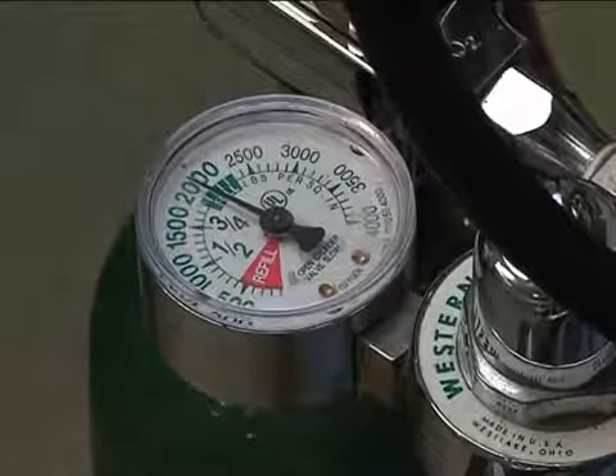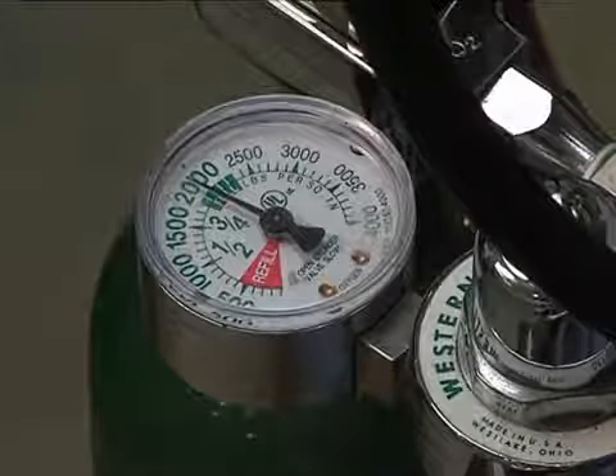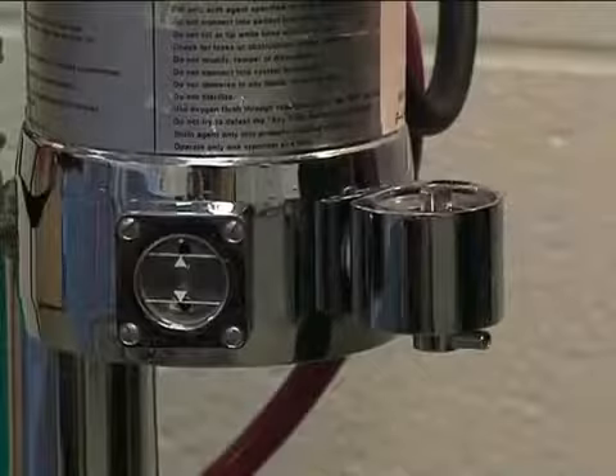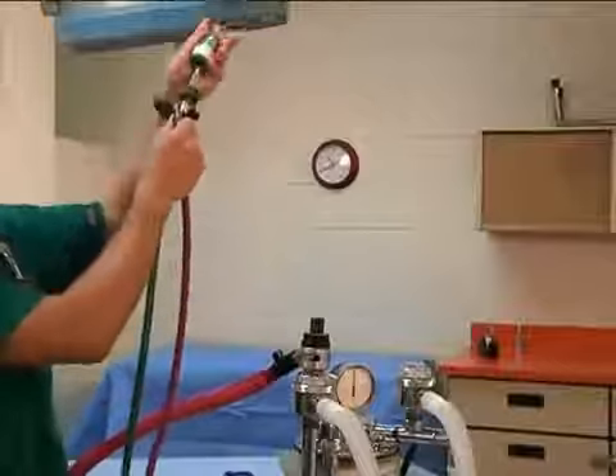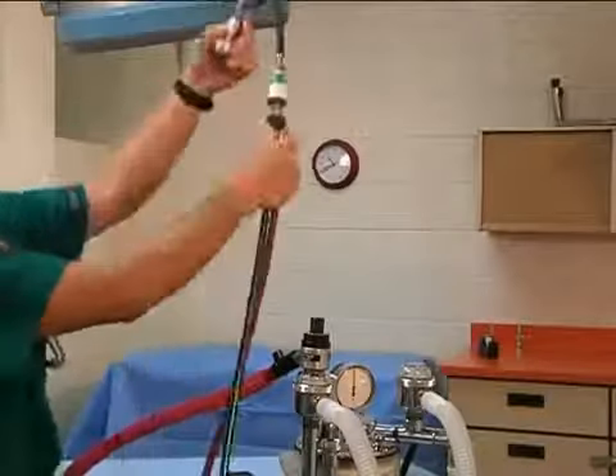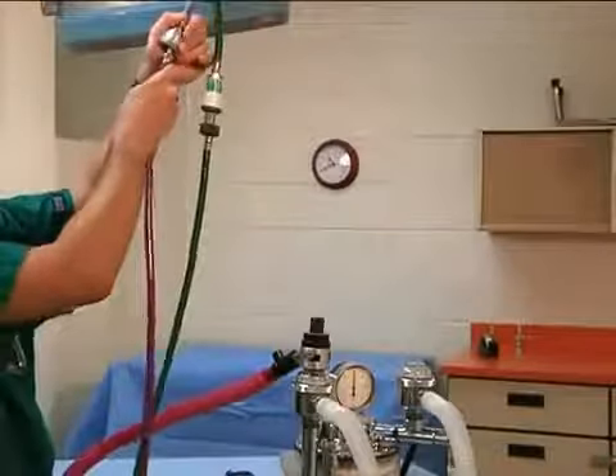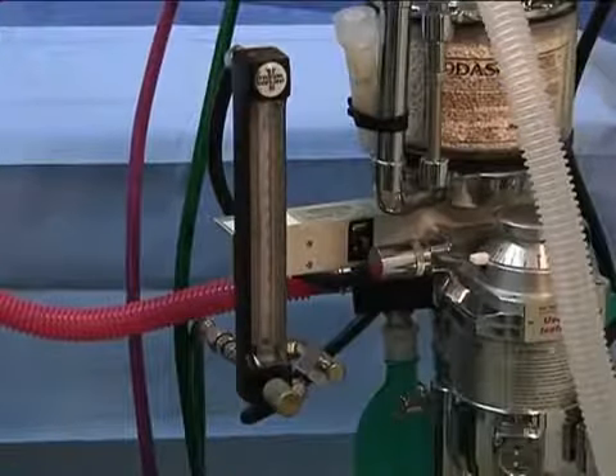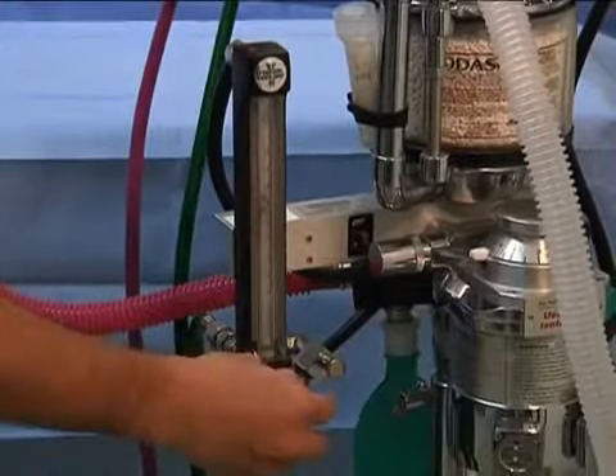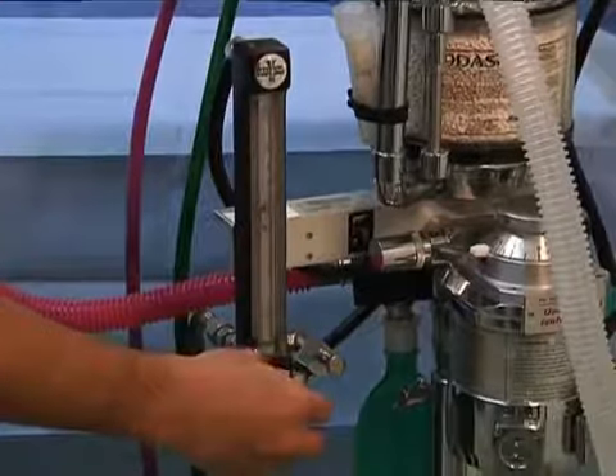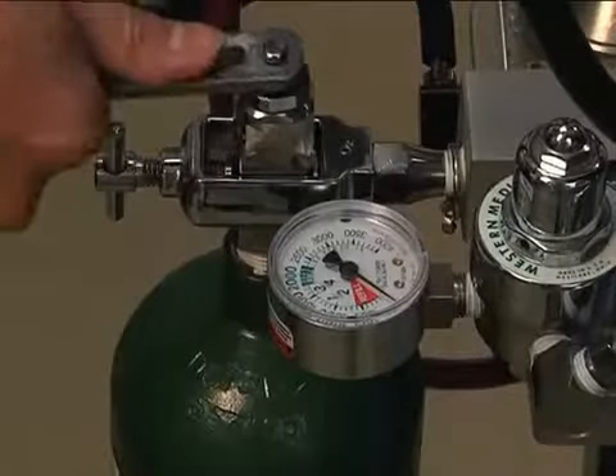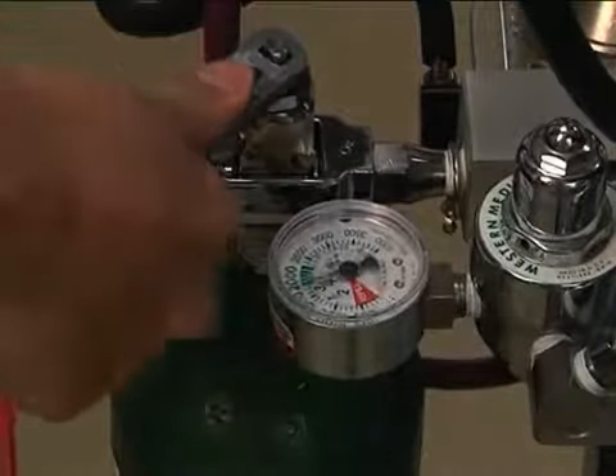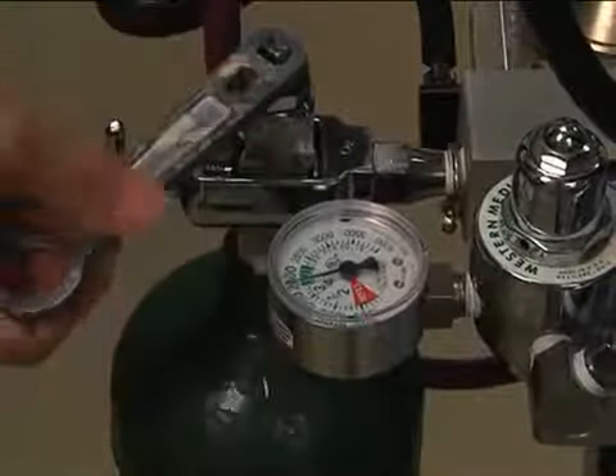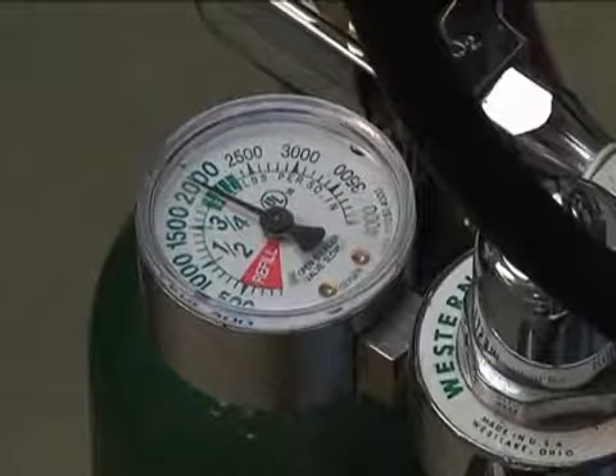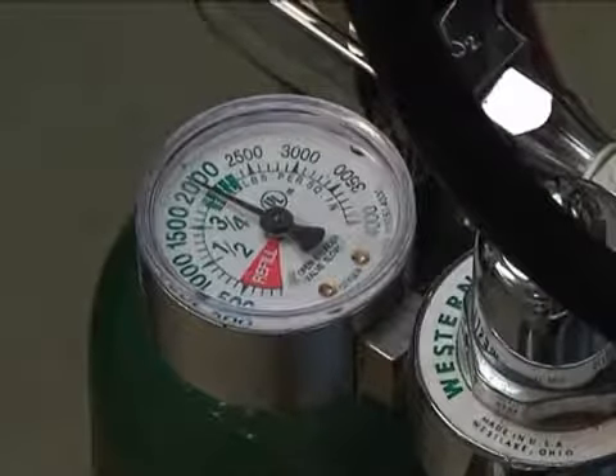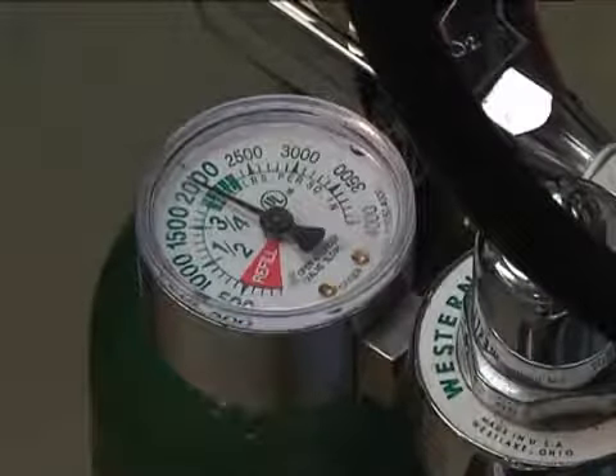Also make sure you have an oxygen supply for your machine and that the anesthetic vaporizer is full. First of all, connect your machine to an oxygen source and the waste gas scavenger system. After connecting to an oxygen source, make sure that oxygen will flow into the system. If there is an oxygen tank on your anesthesia machine, make sure the tank pressure is at least 500 psi. If the oxygen tank pressure is less than 500 psi, replace it with a fully charged tank.